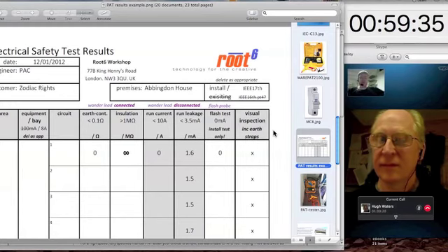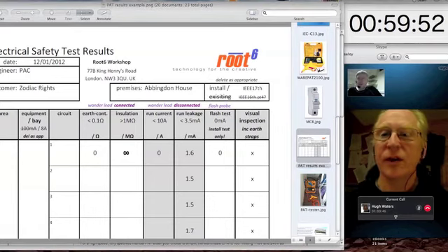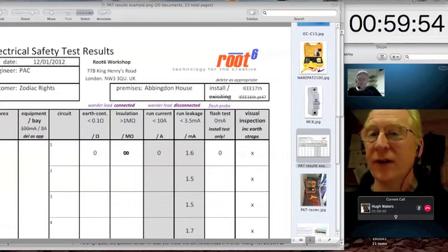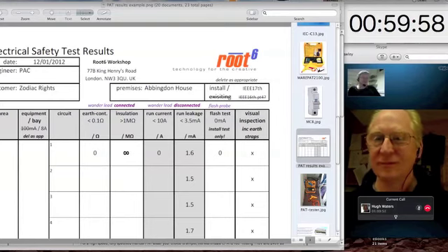Every piece of equipment is connected to the power distribution that's coming out of the bay, which is earthed. And the bays have another path back to earth via the electrician's provided strap, and you've tied all the bays together as well. So you've done as best as you can. There's no more you can do. You really can't overdo it. The more earths you provide, the better things are going to be. Really, braces, another belt, and some more braces. But hey, it's for the sake of a few quid.